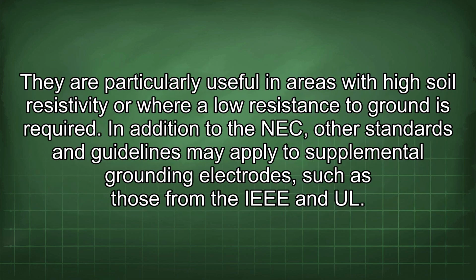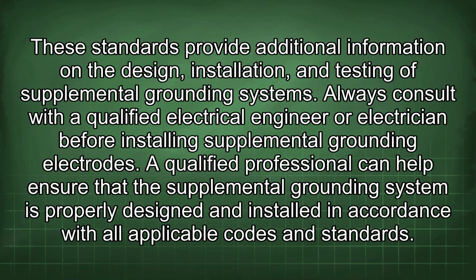They are particularly useful in areas with high soil resistivity or where a low resistance to ground is required. In addition to the NEC, other standards and guidelines may apply to supplemental grounding electrodes, such as those from the IEEE and UL. These standards provide additional information on the design, installation, and testing of supplemental grounding systems. Always consult with a qualified electrical engineer or electrician before installing supplemental grounding electrodes.